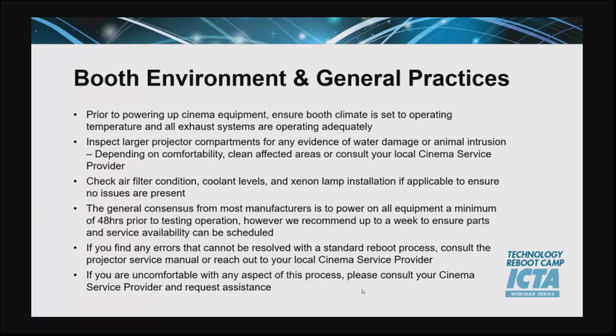If you have a xenon lamp setup, check and make sure it's properly installed and ready to go before firing it up. In most of our discussions with manufacturers, the general consensus is 48 hours prior to testing that everything should be powered on. Looking at the bigger picture, we're probably looking at a week or longer, to make sure you have every opportunity to get your equipment up to speed. If you run into issues, you'll have the ability to get parts and get your cinema service provider field technicians out to do service work, preventative maintenance, and so on. A majority of this can be handled at the booth level, but if you're uncomfortable with any aspect of this process, please consult your cinema service provider or manufacturer to request assistance.